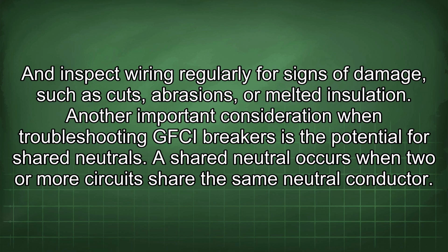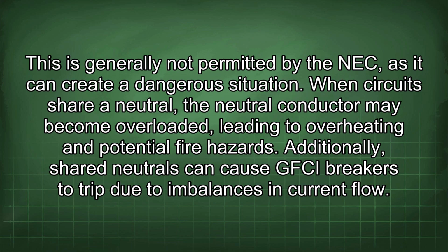Another important consideration when troubleshooting GFCI breakers is the potential for shared neutrals. A shared neutral occurs when two or more circuits share the same neutral conductor. This is generally not permitted by the NEC as it can create a dangerous situation. When circuits share a neutral, the neutral conductor may become overloaded, leading to overheating and potential fire hazards. Additionally, shared neutrals can cause GFCI breakers to trip due to imbalances in current flow.